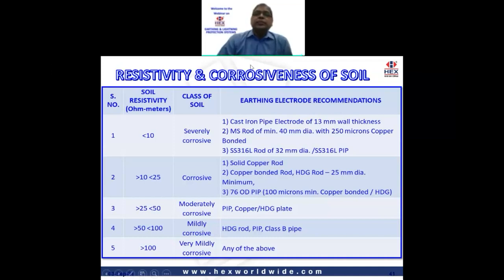Secondly, when a GI pipe is cut to the required length, the cut surface area does not have the zinc coating on it, and the corrosion will start from there. I think you are all aware of this. Our earthing electrodes are hot dip galvanized after the fabrication process is completed. So the inner pipe, the inner cavity, the outer pipe, and the top terminal of the pipe in pipe are all hot dip galvanized after they have been fabricated and welded. Now this, of course, will increase the cost to some extent, but it definitely increases the quality and the life of the electrodes.